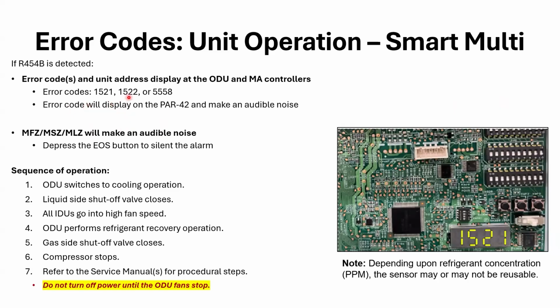So error code 1521, 1522, or 5558. The error code will display on the PAR-42 and make that noise we talked about. This is new here. To make that noise stop, you can depress the EOS button on that particular unit. That's the emergency operation switch, if you're familiar with that on those wall units. We can put that in test mode, right? We use that for emergency operation of cooling or heating. So that will silence that alarm.